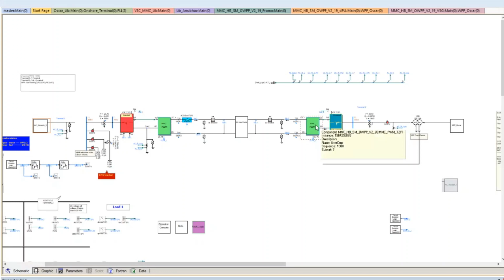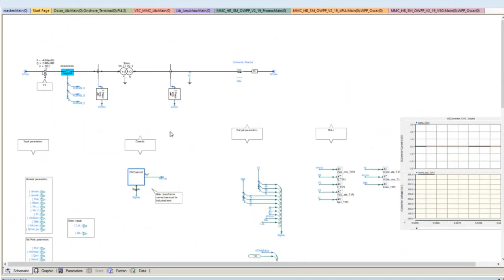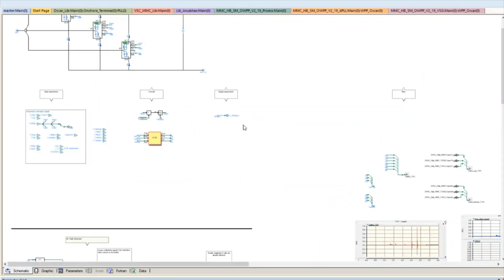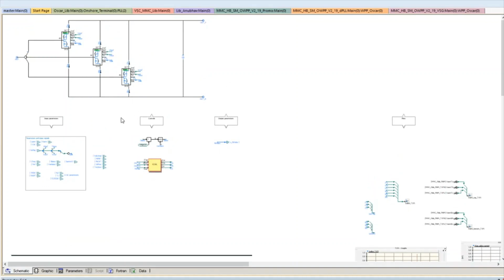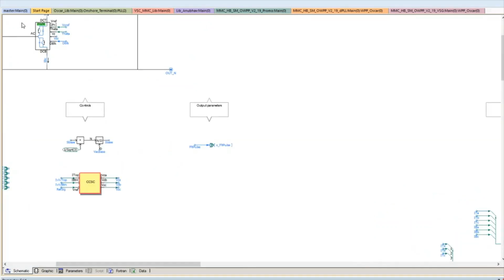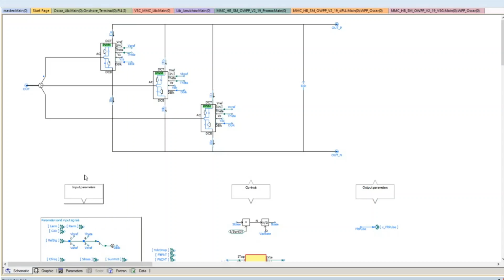Now both MMC terminals are the same. So you have the MMC control in this block here, with the converter transformer and the converter reactor, with the PIR if needed. Each MMC is modeled with a detailed equivalent model. Each arm consists of 225 submodules, but during the modeling they are grouped together to solve the circuit, and then the group model is split again so that we can see what's happening inside the submodules.